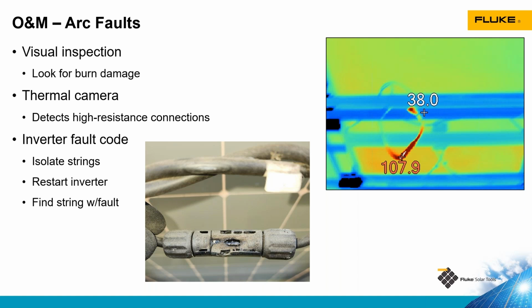Inverters have arc fault protection built in, all modern inverters at least. If the inverter throws a fault code, what you can do is a troubleshooting process where you eliminate sections of the array, turn the inverter back on, see if the fault code comes back. If it doesn't, you know the fault is in that section of the array that you isolated. If it does come back, you know it's not that section, so you can reconnect it, shut the inverter off, disconnect a separate section of the array, and turn the inverter back on and see if the fault code goes away. By doing that, you can do a process of elimination to figure out where the fault is.